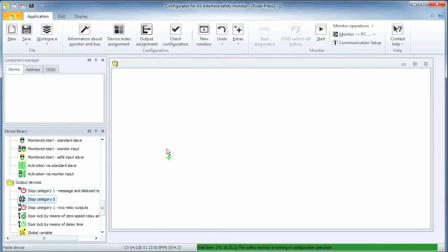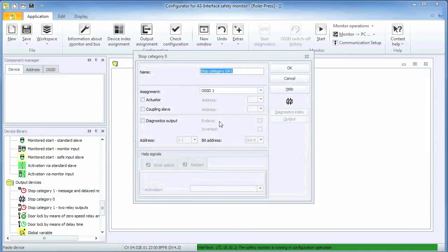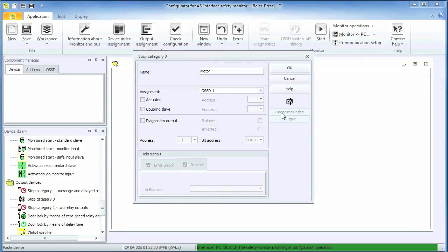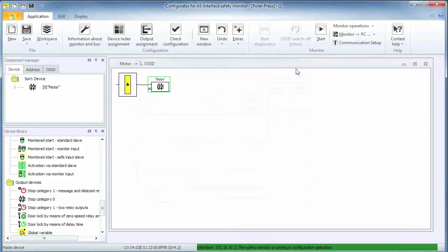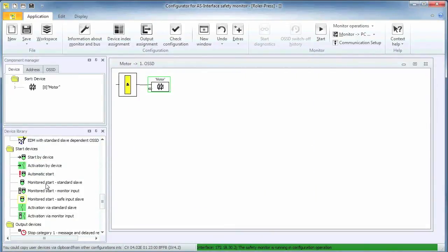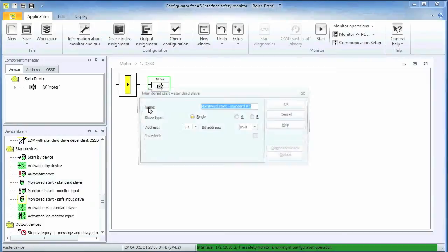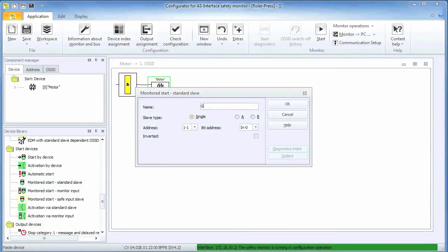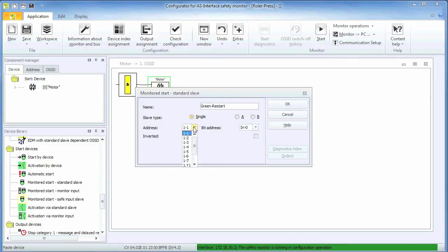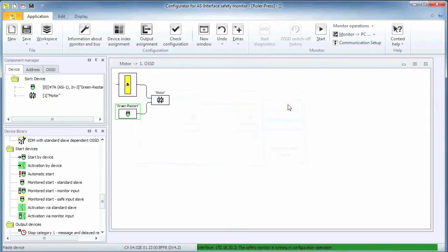I usually start by selecting the output first, a category zero, immediate stop in this case. Since it is used to remove power from the motor, I call it motor. Next I am adding the restart condition using a standard slave, the push button module with address 7a. The restart operation is associated with the most significant bit in 3.